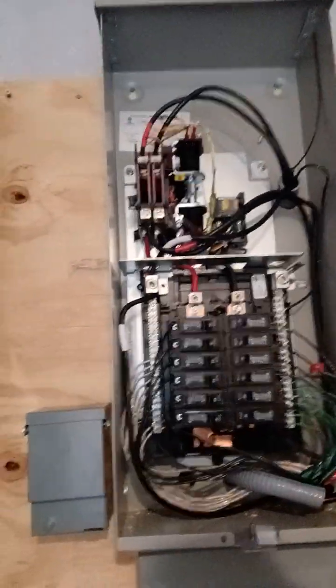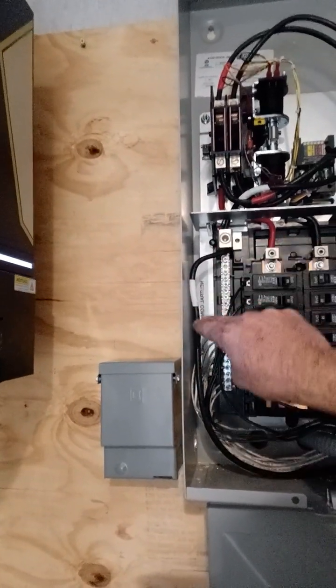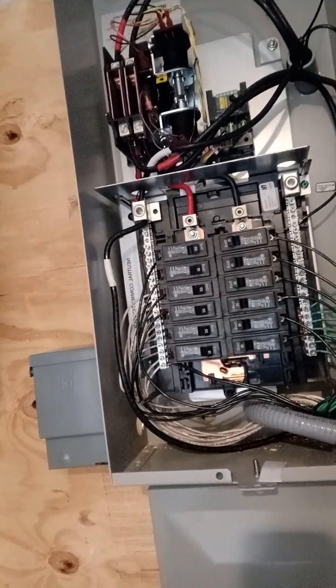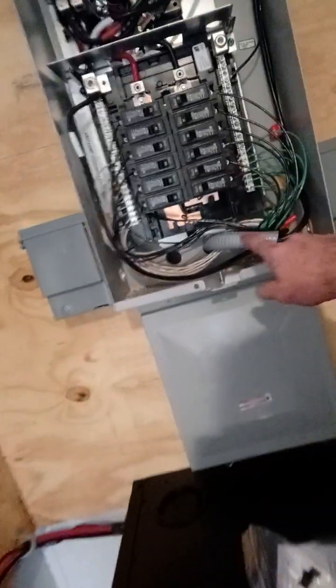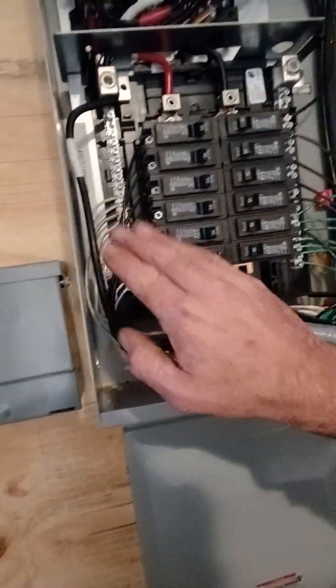This is a power output hub right here. What you're seeing here is the actual inside part of the transfer switch — black and red are labeled for L1 and L2, neutral is always neutral, and ground is always ground. Don't confuse neutral for ground or vice versa, because that's not the way it's supposed to work. We basically took all these switches and transferred them over — lines into lines, ground into ground, loads into loads, and neutral into neutral.